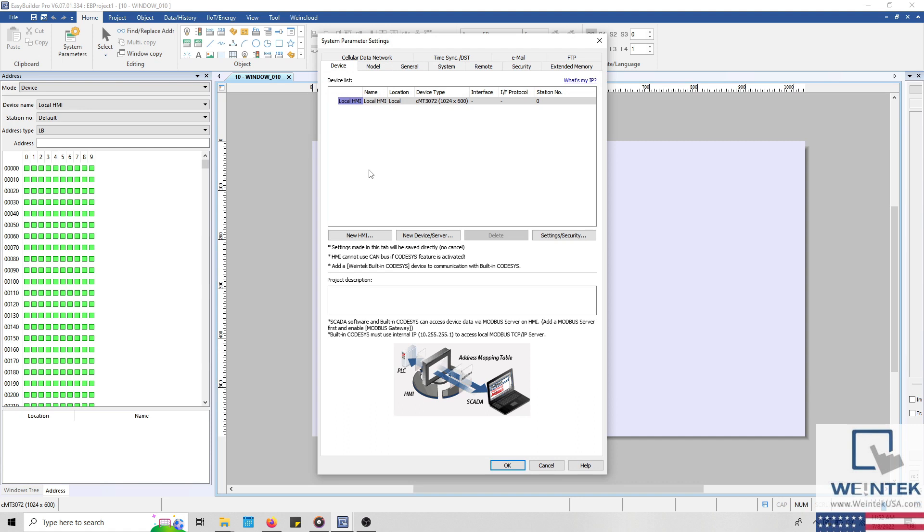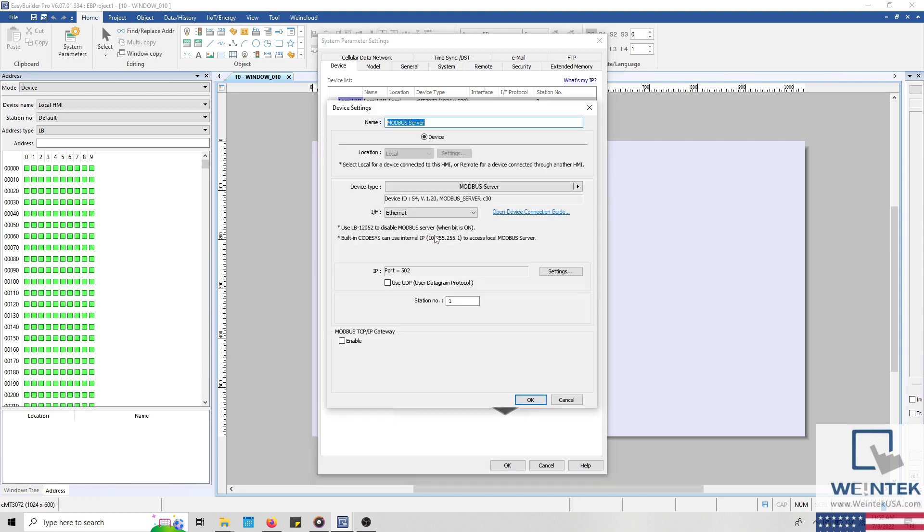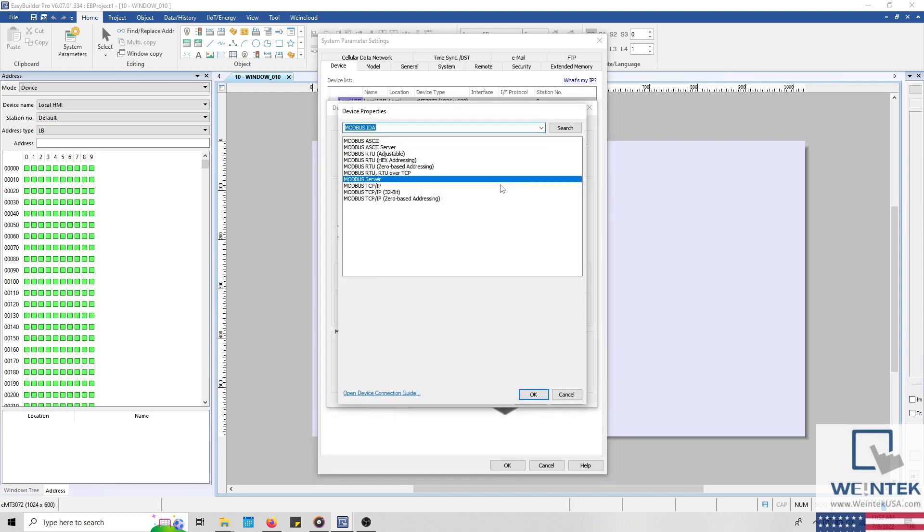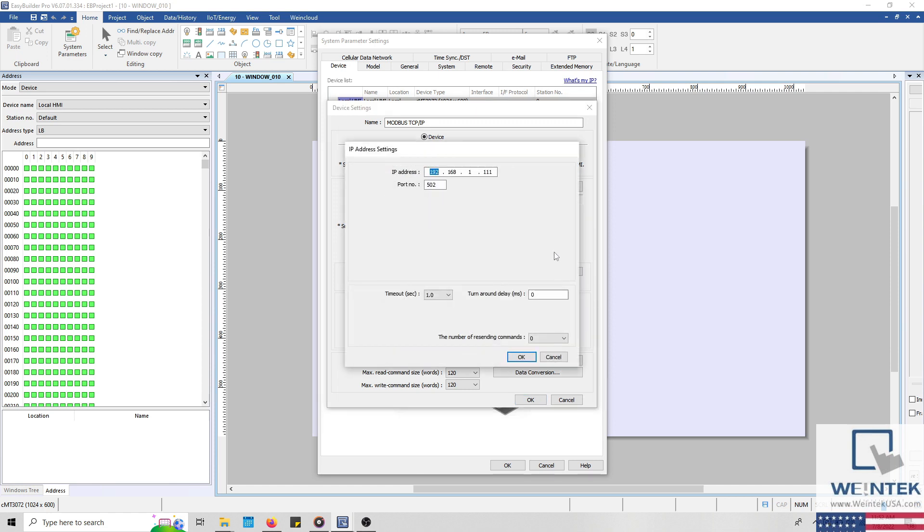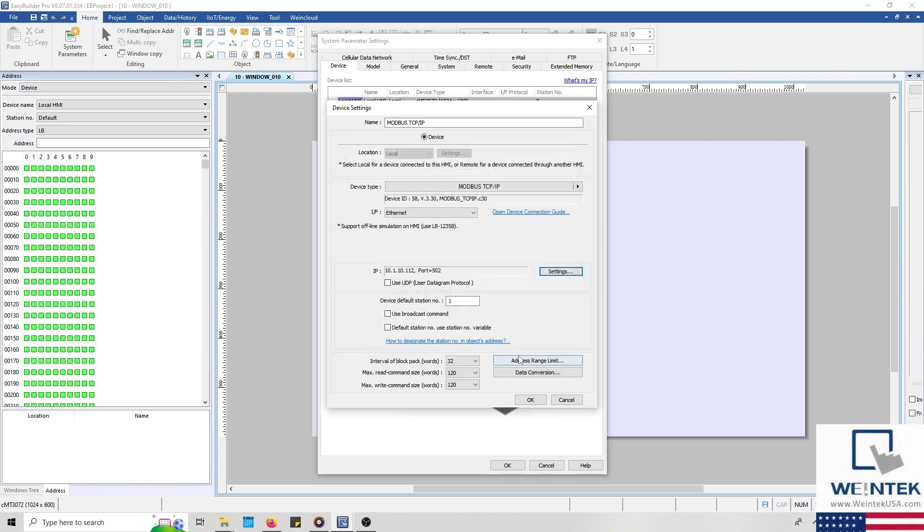And in the same way that we added the Modbus server driver, we'll add the Modbus TCP IP driver as well. I'll define the IP of our Modbus server, and we'll leave the port set to 502 and the station number at 1. This matches the configuration of our server.